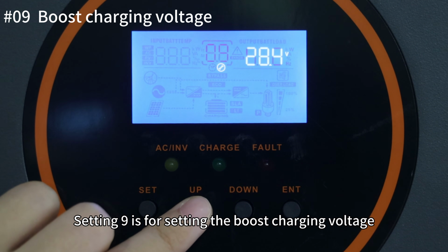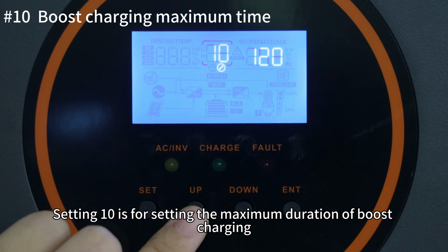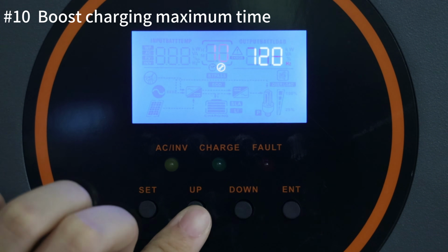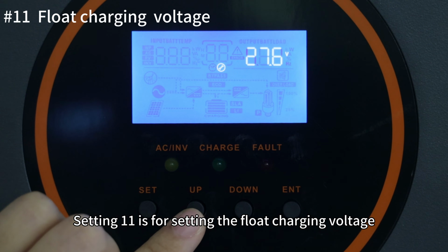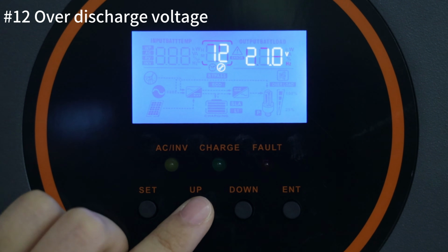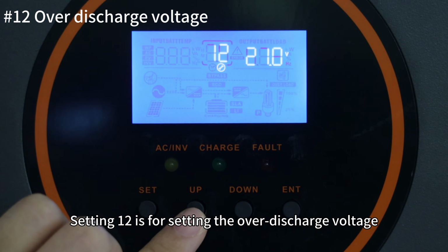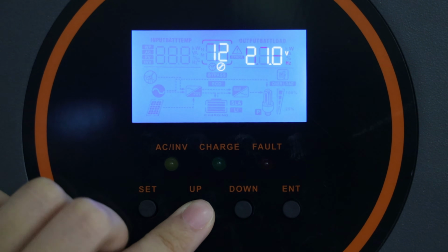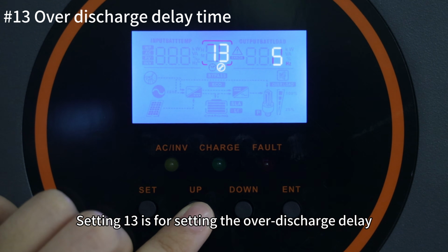Setting 9 is for setting the boost charging voltage. Setting 10 is for setting the maximum duration of boost charging. Setting 11 is for setting the float charging voltage. Setting 12 is for setting the over-discharge voltage. Setting 13 is for setting the over-discharge delay.